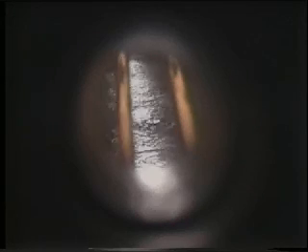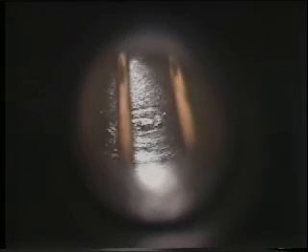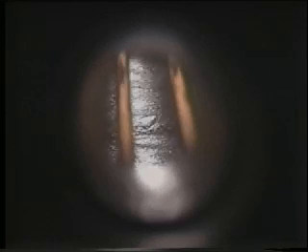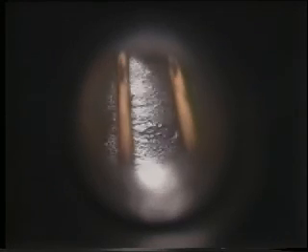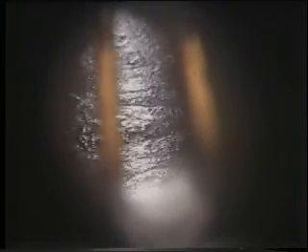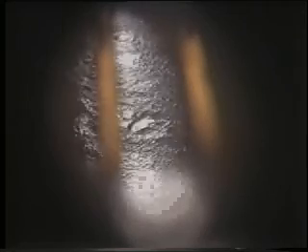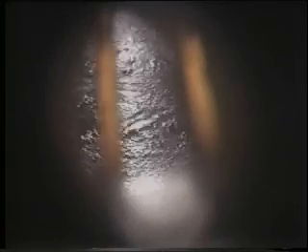If the vessel is to be used as a vapor supply, providing other than very small quantities, a vaporizer is required. For every pound of CO2 vapor that is withdrawn from the storage unit, a portion of the liquid evaporates to fill the void. When any liquid evaporates, a cooling effect takes place. With carbon dioxide at 0 degrees Fahrenheit, the result is, with each pound of vapor withdrawn from the storage unit, approximately 120 BTUs are thus removed. The heat is removed from the contained liquid, with resulting decrease in temperature and pressure.